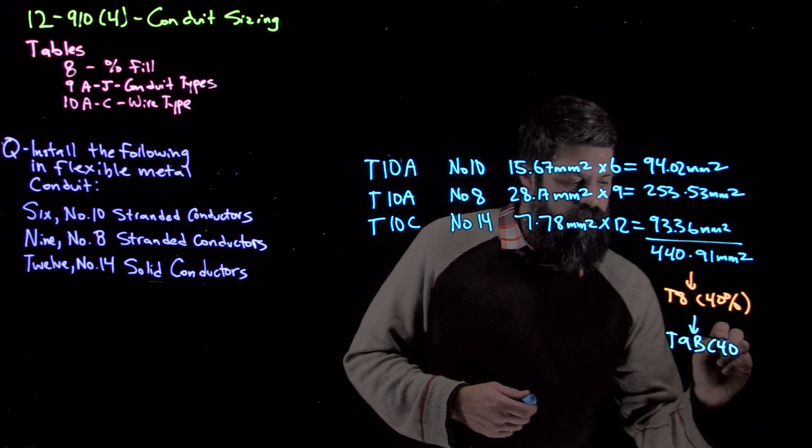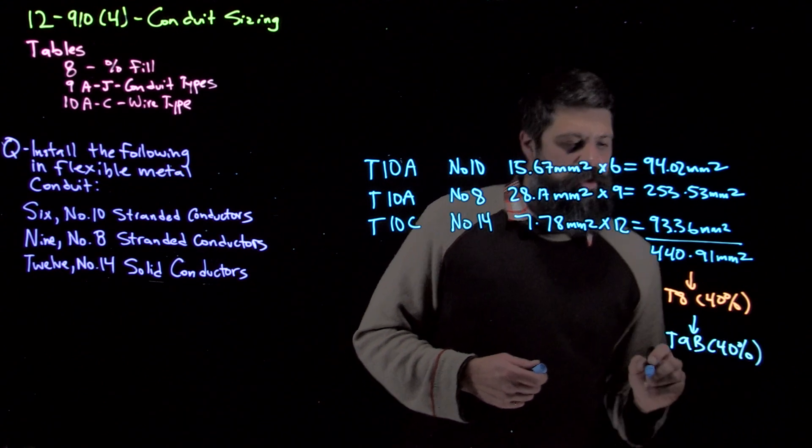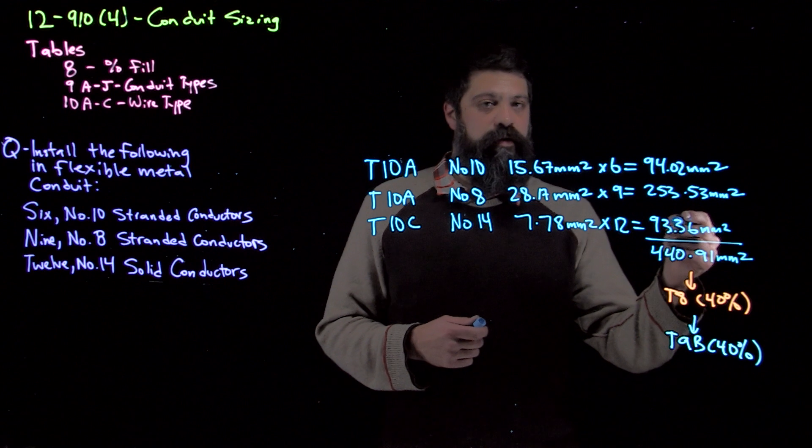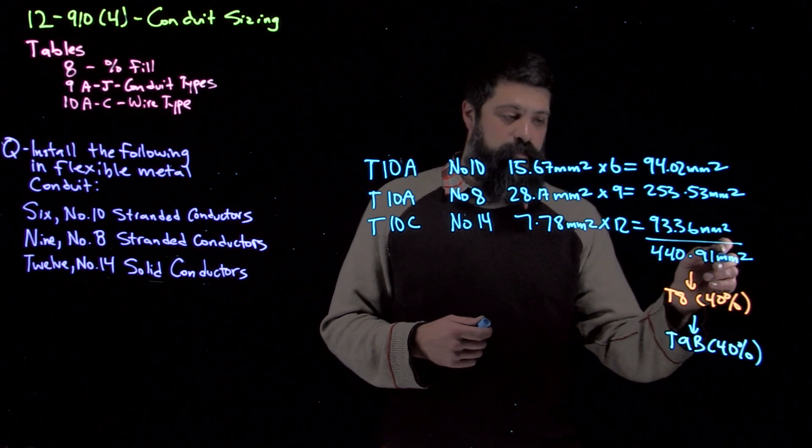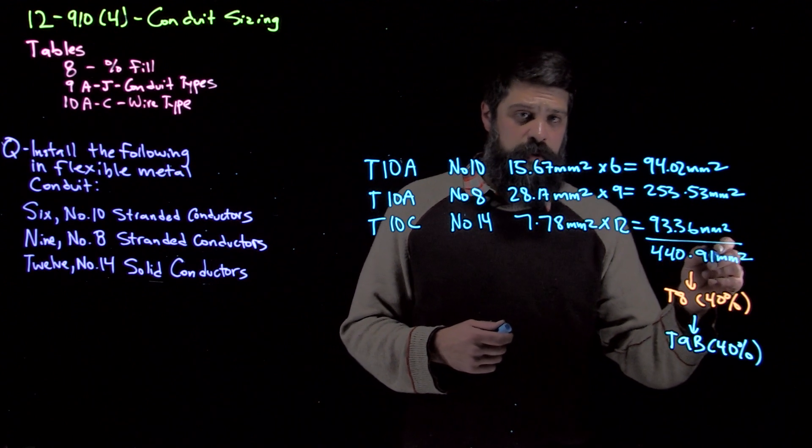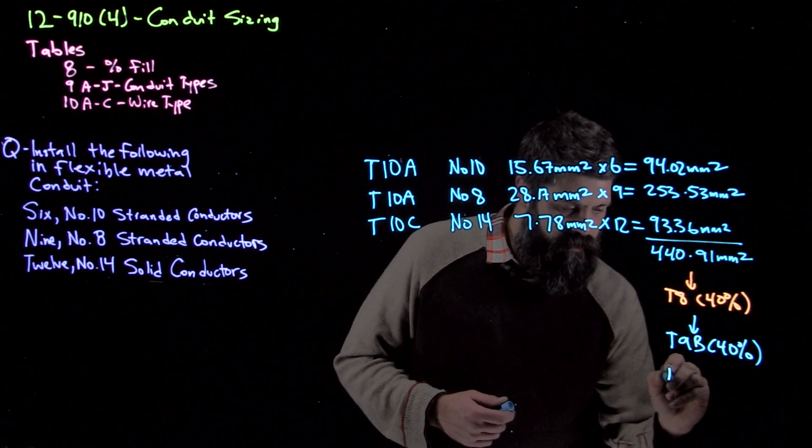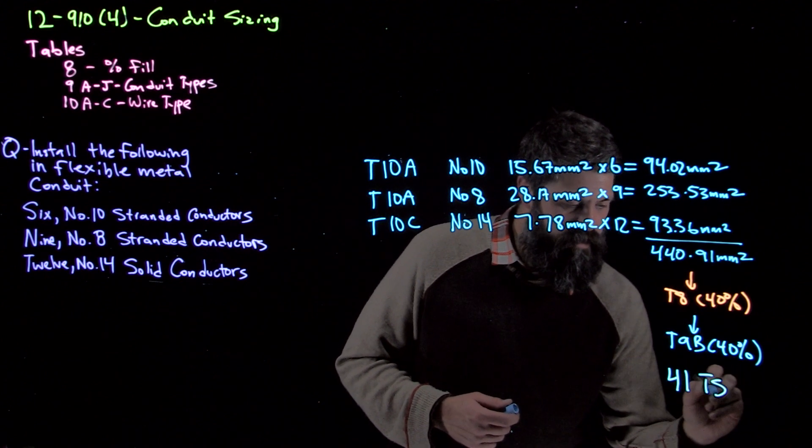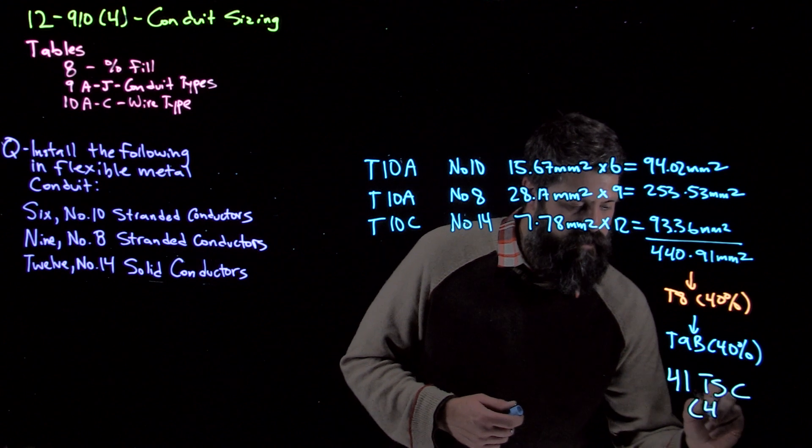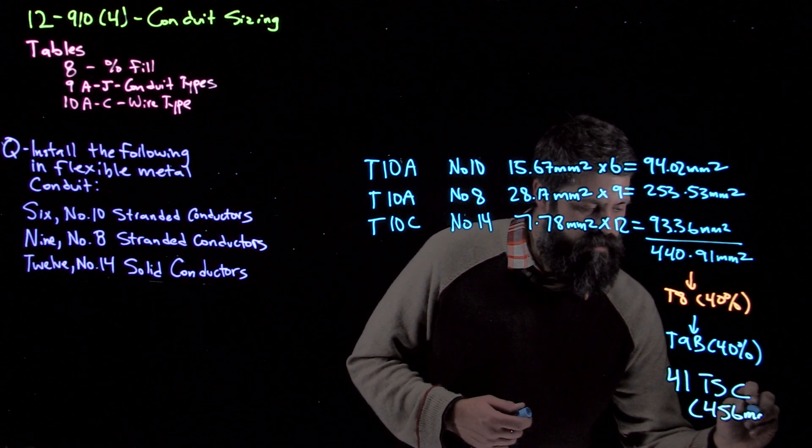And in the 40% column, we're looking for a number as big or bigger, the next size up from this 440.91 mm². That's going to take me to a 41 trade size conduit, which is good for 456 mm².